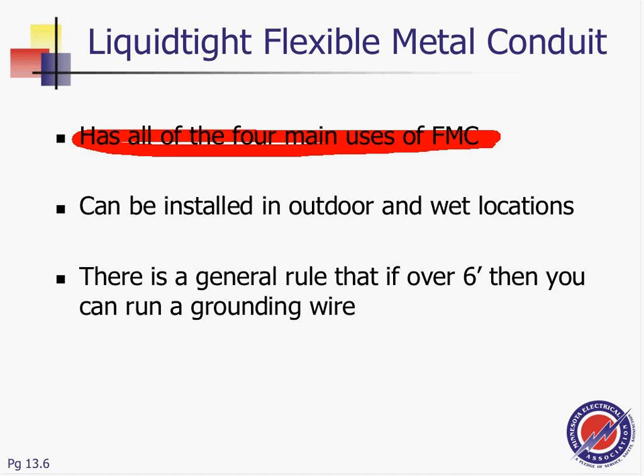Let me ask you this question: how many of you guys have installed this wiring system, flexible metallic conduit or Liquidtight? How many of you have installed Liquidtight flexible metallic conduit? Commonly used in residential to tie the air handling, the air conditioning to the disconnect, units, air units, pumps. If in a wet location, that's basically where you use flex.